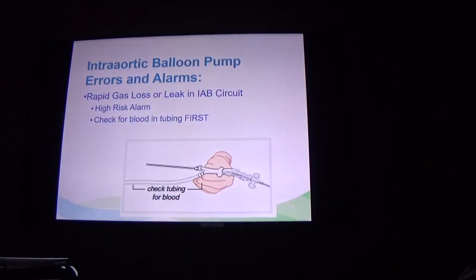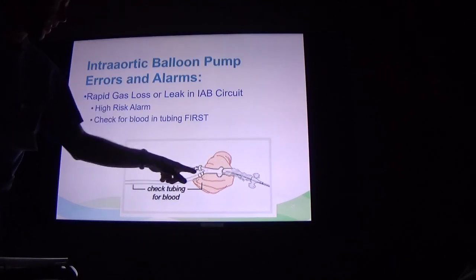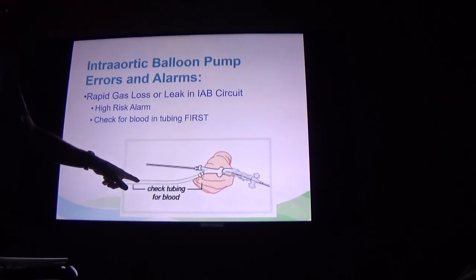A rapid gas loss or leak, again, that can happen from a disconnect, but the most important thing is to check the tubing. And if there's blood in this tubing here that runs off the IABP catheter, that's a bad sign. It means the balloon is probably ruptured and you can't use this device. So it means immediately putting it in standby, no longer pumping until they can replace the device.